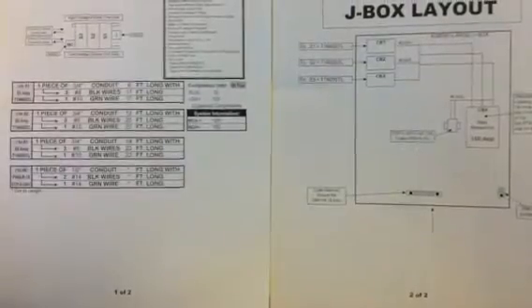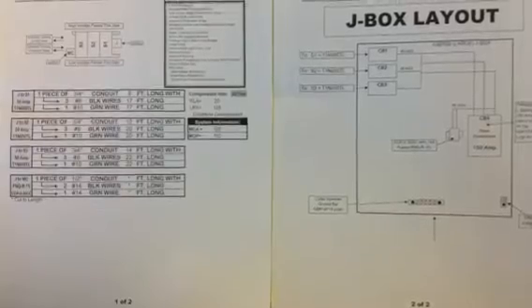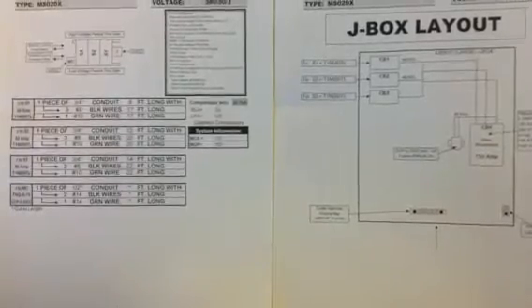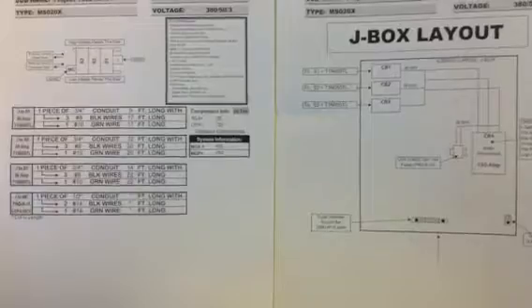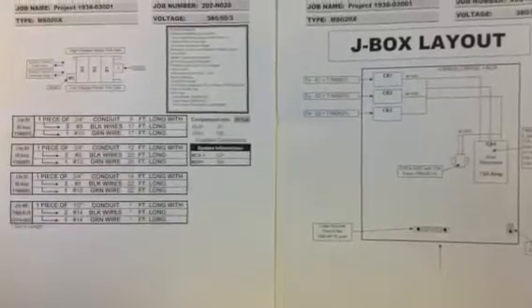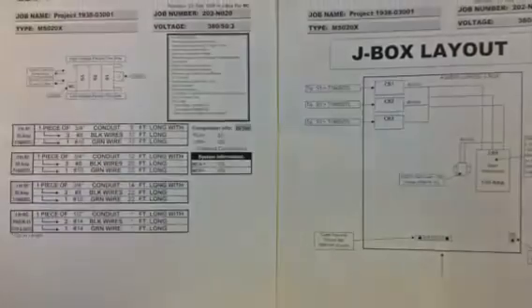This is a close-up of the wire cut list. The markings on this page correspond to the markings on the gray seal-tight conduit that run throughout the chiller. This should be used for take-apart and reassembly.